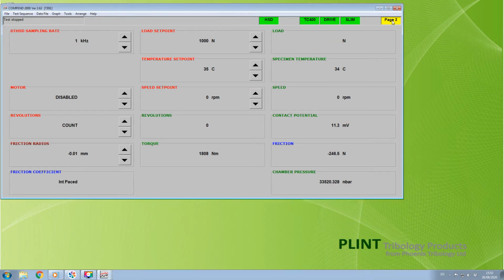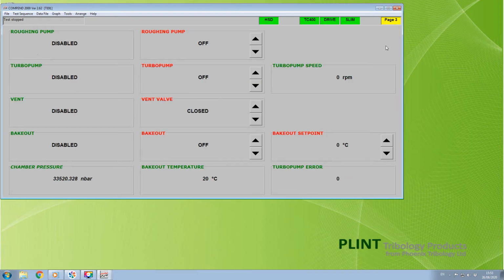To operate the vacuum system, navigate to the page 3 screen to access the relevant control functions. The on-off switches send requests to the vacuum controller, and the enable-disable boxes display the corresponding response. Four software functions are available. Roughing pump. This starts and stops the roughing pump. There will normally be no delay between switching on the pump and the response indicating that the pump has been enabled.